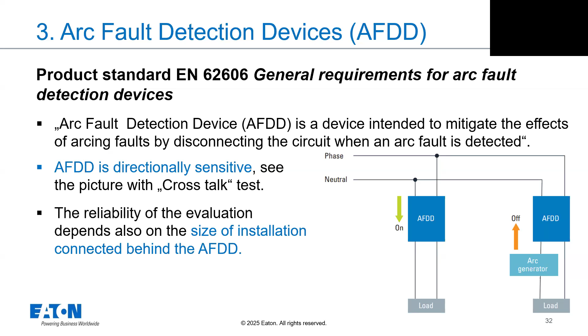Then it's also related to reliability of evaluation. It's good to point out that reliability of evaluation of an AFDD is dependent on the number of loads on the secondary or output side of the AFDD. The best is to use very short installations or a limited number of loads. It doesn't make big sense to use one AFDD for a complete installation, for example, because it will be a very complicated life for the AFDD to detect a signal.